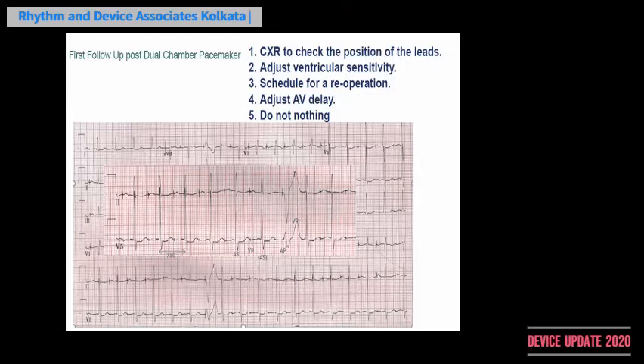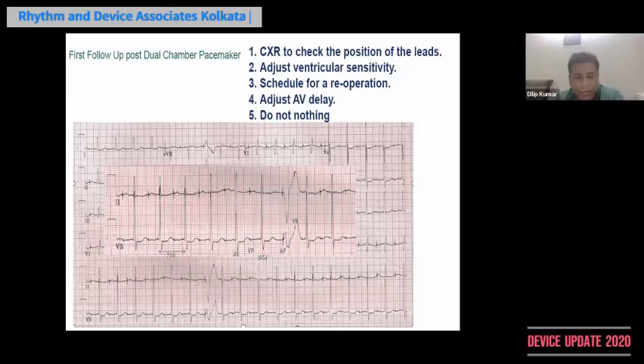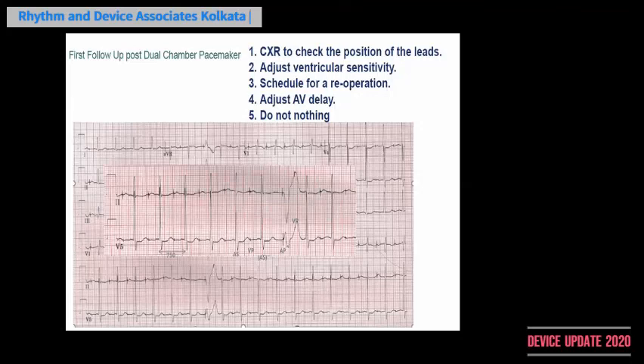Sir, Dilip sir, you see the lead 2. You get a pace, sense, A pace, sense, A pace, sense, A pace. Suddenly you get a VPC. Can't it be that there is an atrial spike, then a V pace after the paced AV delay, which has come on the T wave? You get a VPC, and at the same time the atrial spike gave a spike, and then at the paced AV delay, whatever is set, 200, it has come as safety pacing.